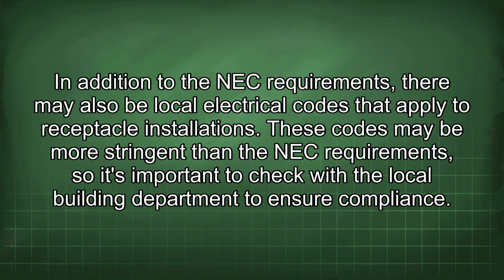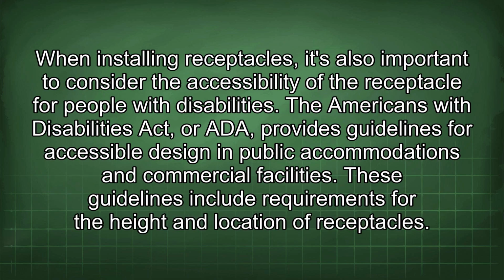In addition to the NEC requirements, there may also be local electrical codes that apply to receptacle installations. These codes may be more stringent than the NEC requirements, so it's important to check with the local building department to ensure compliance. When installing receptacles, it's also important to consider the accessibility of the receptacle for people with disabilities. The Americans with Disabilities Act, or ADA, provides guidelines for accessible design in public accommodations and commercial facilities. These guidelines include requirements for the height and location of receptacles.